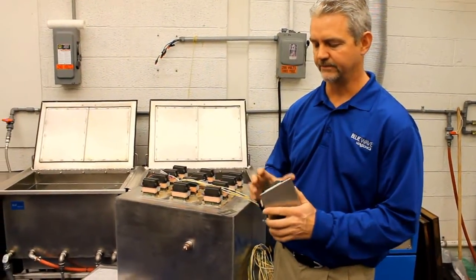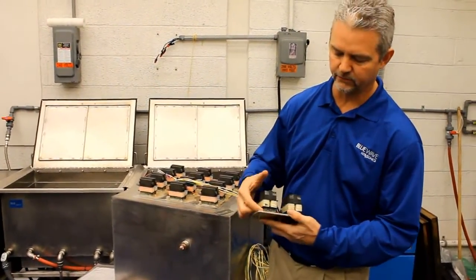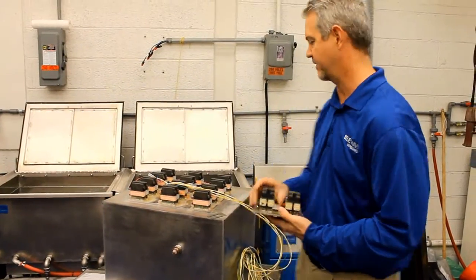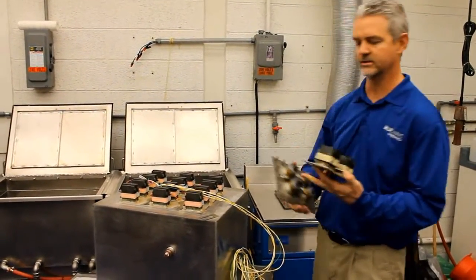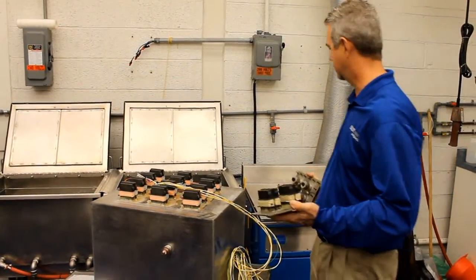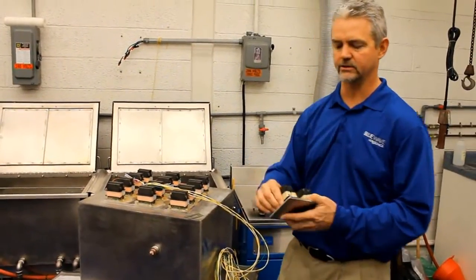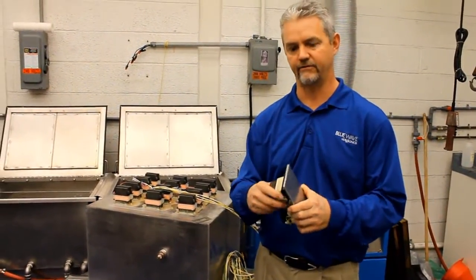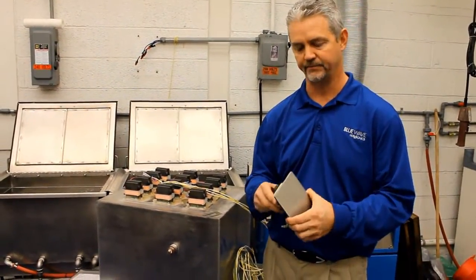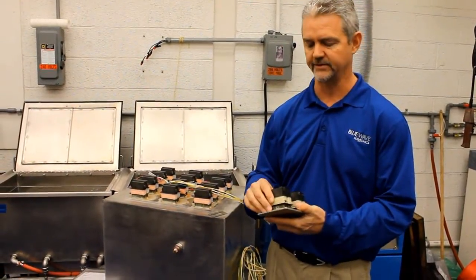The other advantage of this type of transducer is that we can silver-braze it onto the radiating diaphragm, unlike the epoxy bond. With this silver-braze, there's no way that this transducer is ever going to dis-bond from this radiating diaphragm, which is essential in the performance of cavitation.